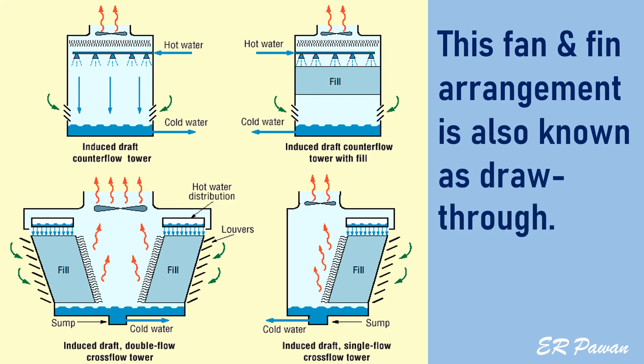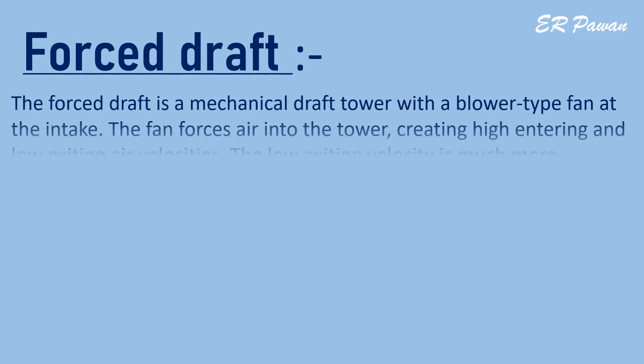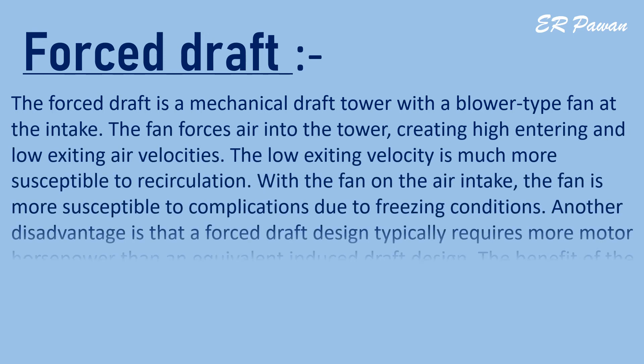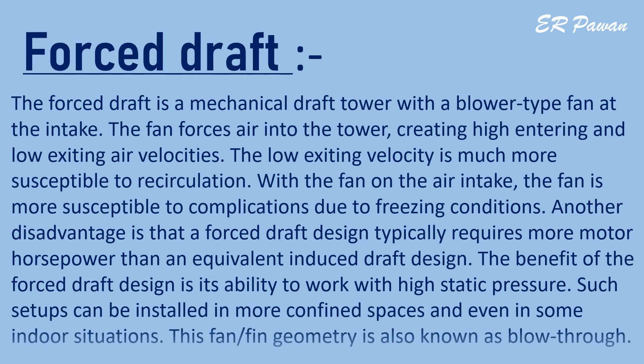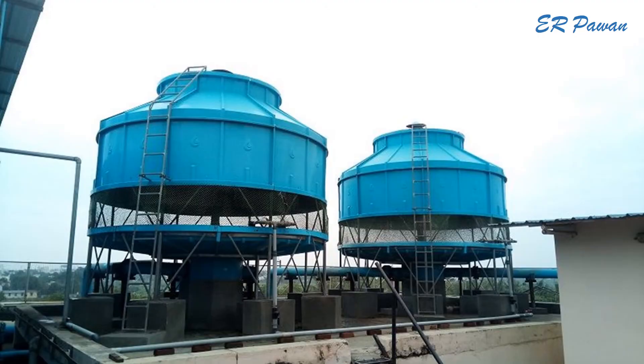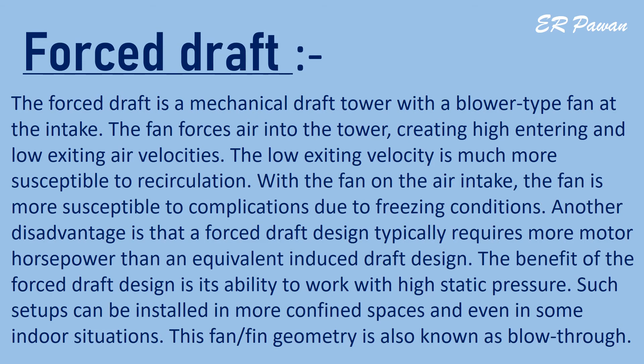Forced draft: the forced draft is a mechanical draft tower with a blower type fan at the intake. The fan forces air into the tower, creating high entering and low exiting air velocities. The low exiting velocity is much more susceptible to recirculation. With the fan on the air intake, the fan is also more susceptible to complications due to freezing conditions. Another disadvantage is that a forced draft design typically requires more motor horsepower than an equivalent induced draft design. The benefit of the forced draft design is its ability to work with high static pressure, allowing installation in confined or even indoor spaces. This arrangement is also known as blow-through.